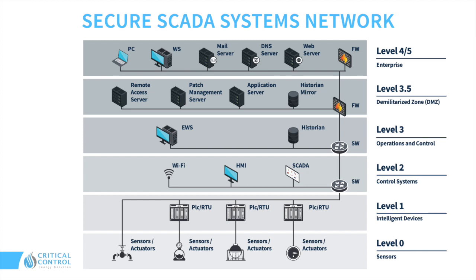Those databases connected to your control system at level two, and then you have those connected eventually to your PLCs, your RTUs, your EFM devices in the field, which are finally at the bottom layer — report level zero, your ground level — which would be your instrumentation devices: those transmitters, pressure transmitters, transducers, that would actually provide the raw information.